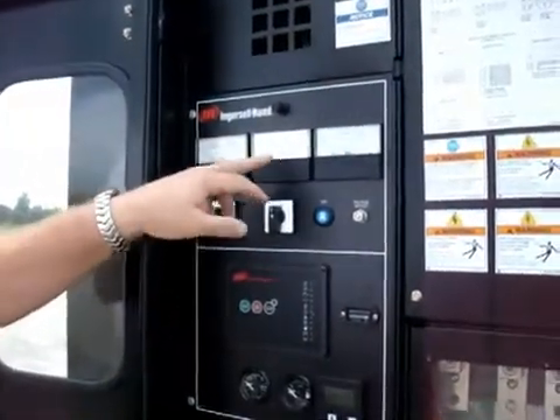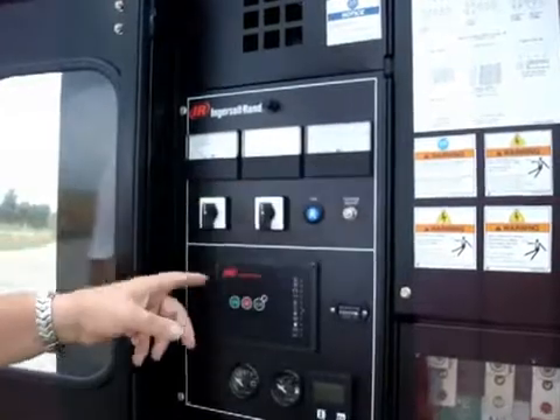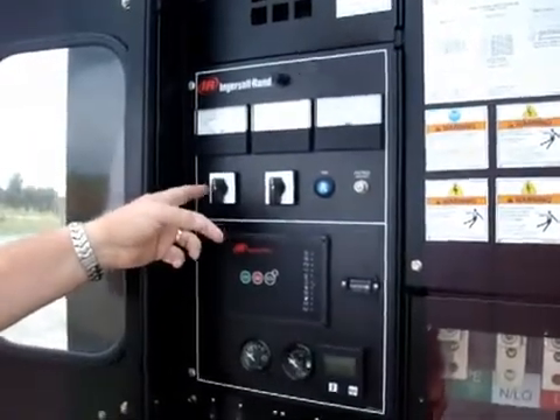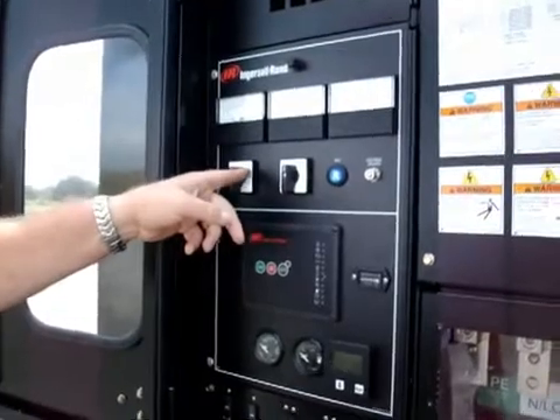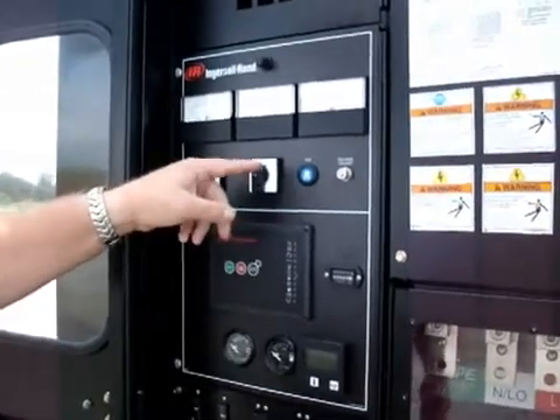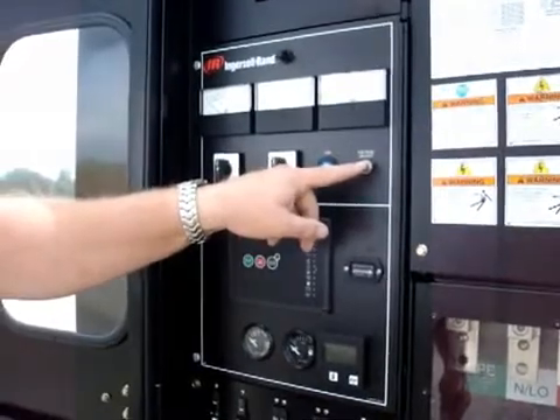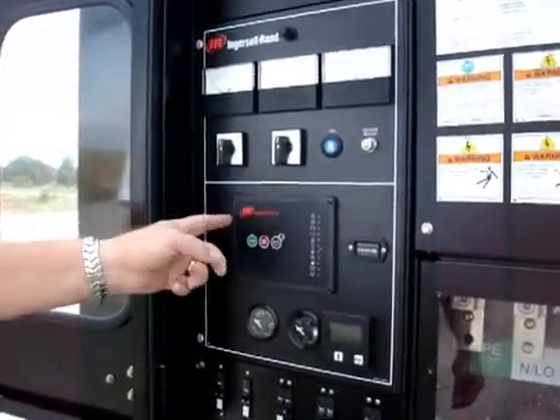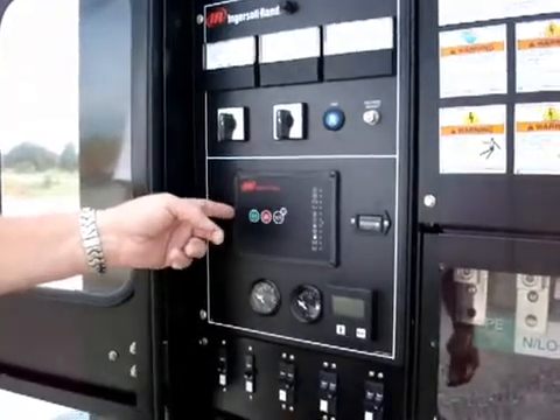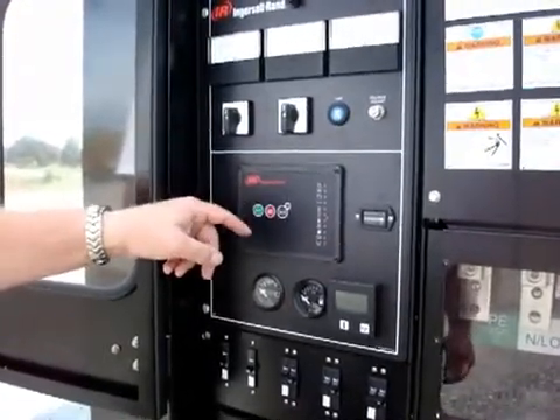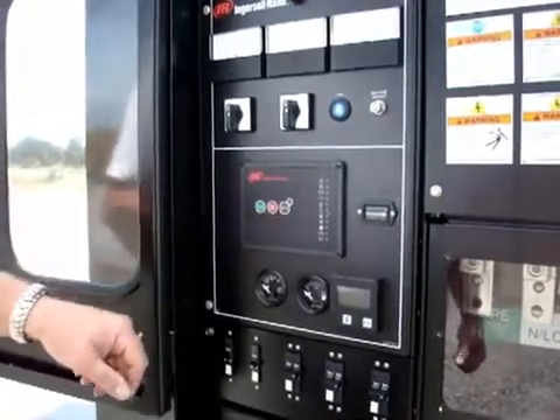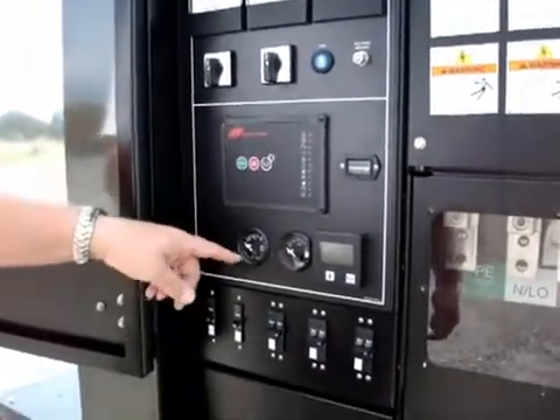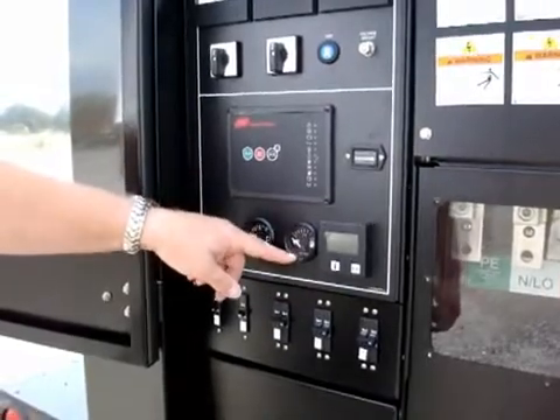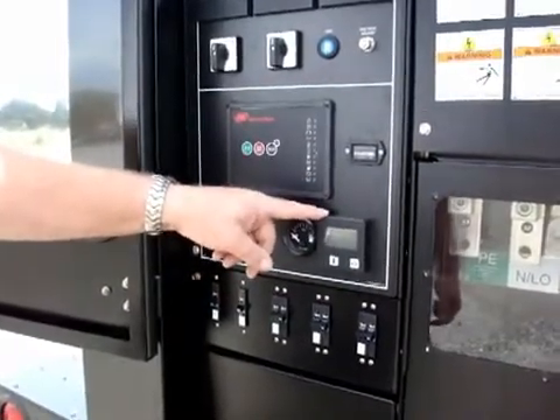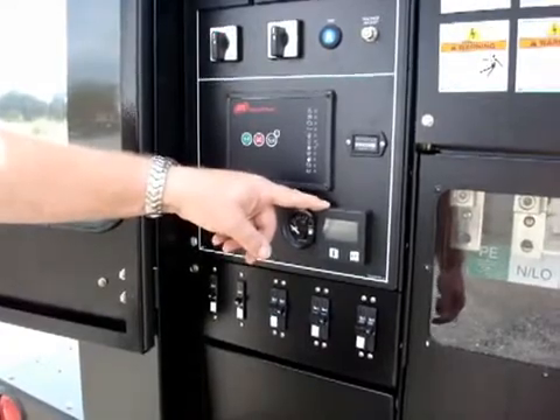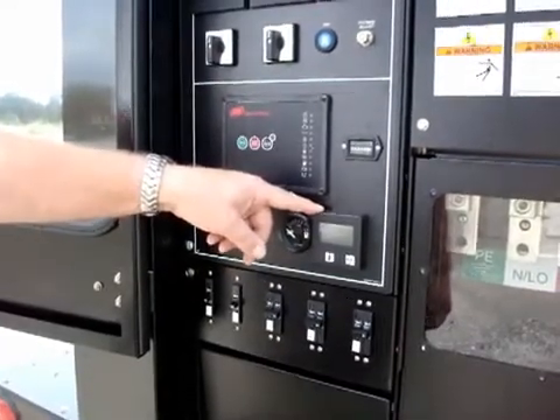We have a voltmeter, an ammeter, and a frequency meter, a voltage selector switch to determine line to line and line to neutral voltages, our three-phase currents, and the voltage adjust potentiometer. This is the IntelliSys controller that we'll use to control the machine, with both the start/stop button and an auto start button. Hour meter, battery voltage, fuel level, and this gives us any indications of engine faults on the ECU located for the engine control.